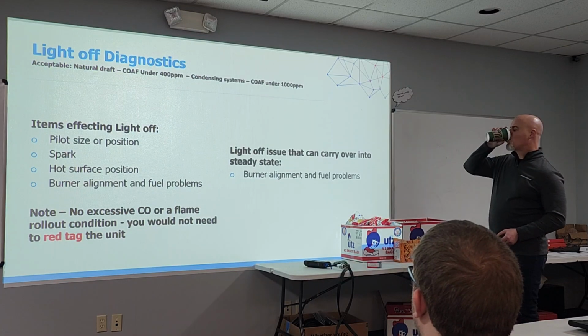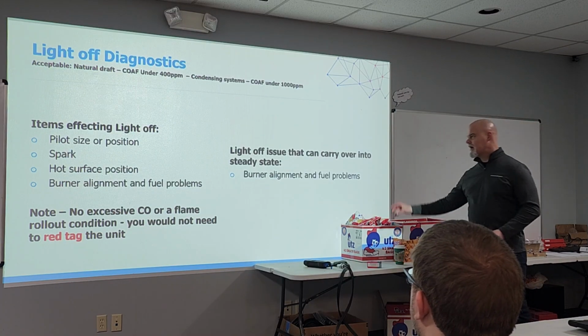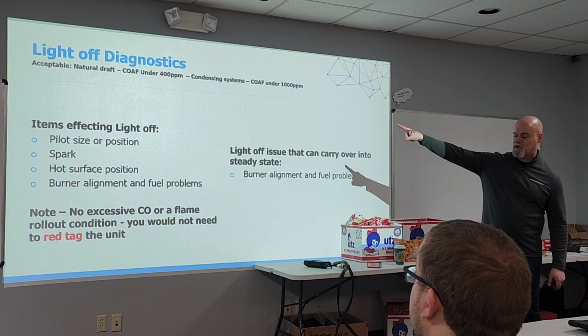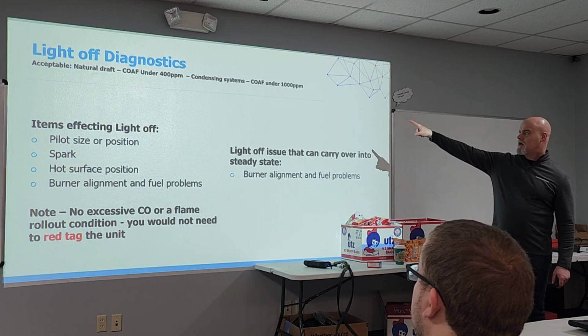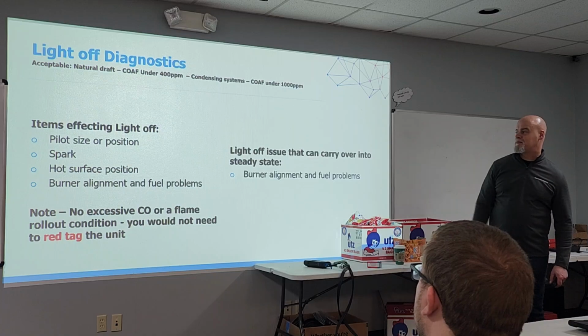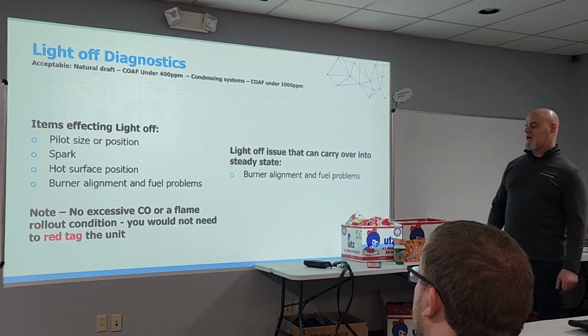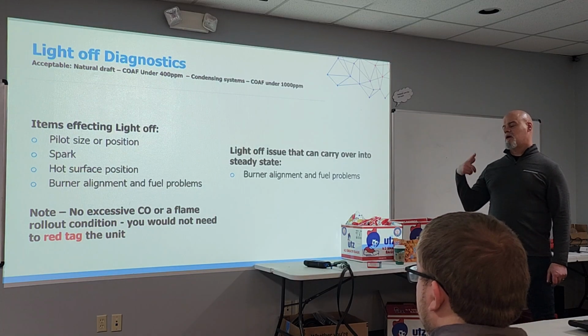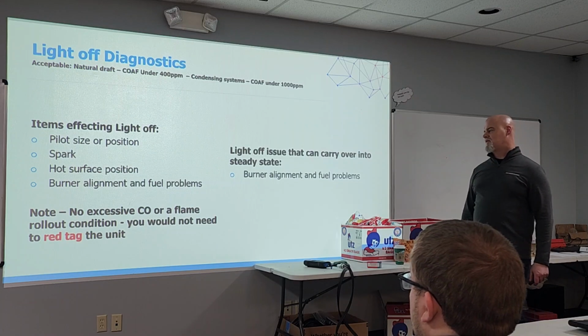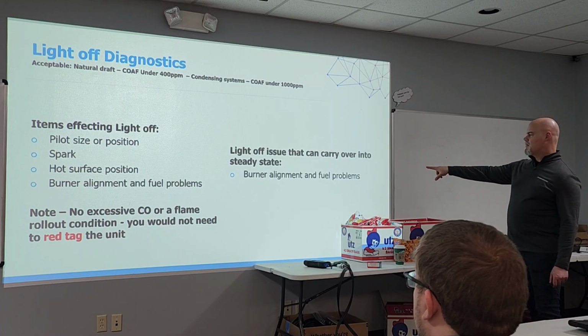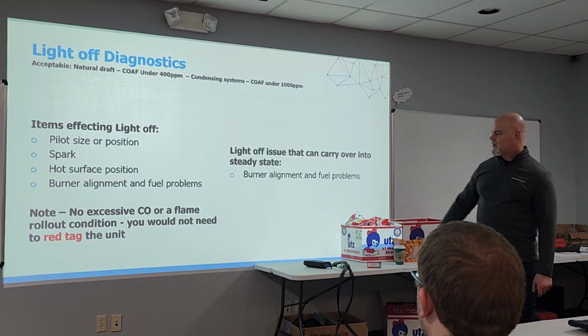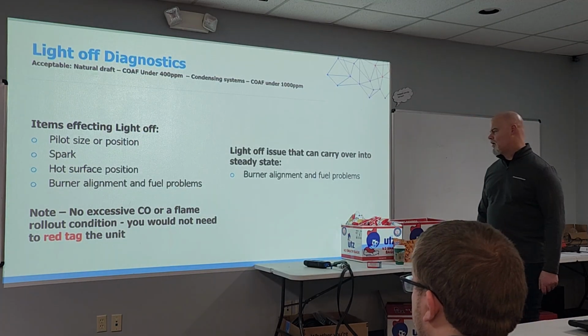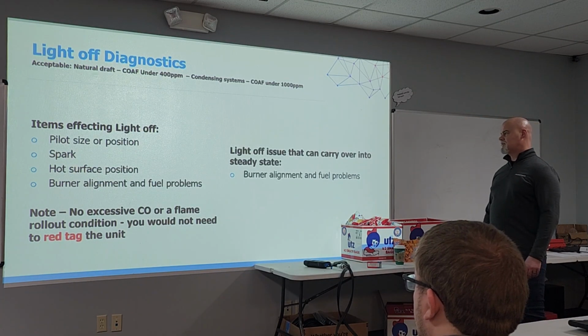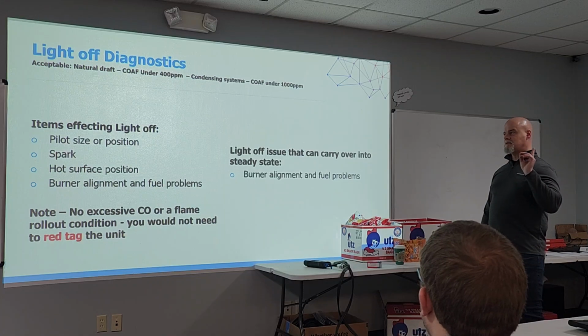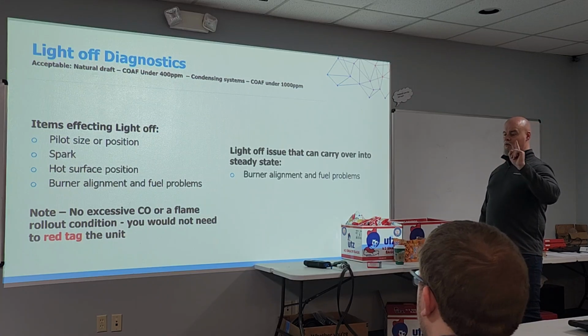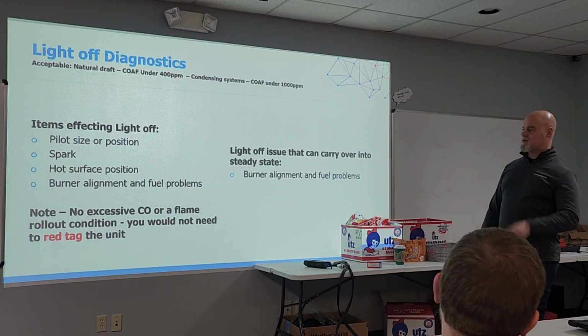So we're looking at CO air free for natural draft under 400 ppm, like I talked about earlier, and condensing systems under 1000 ppm. Items affecting light off: pilot size or position, spark, hot surface position, burner alignment and fuel problems. Burner alignment and fuel problems can show up in steady state as well. If there's no excessive CO or rollout condition, you would not need to red tag this system. But it's very important that we look at the tells of light off, so we know whether we need to stop the process.